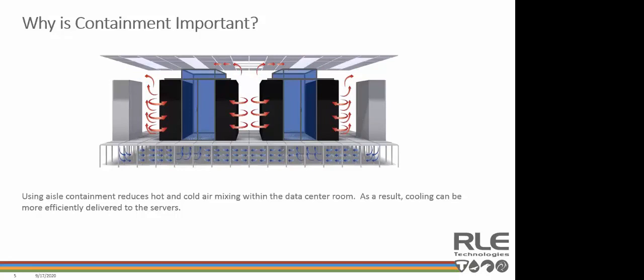In a properly contained space, cold air supply and warm air return remain separated, as you can see in the image here on this slide. This increases cooling efficiency. Ideally, cold air is only able to move through the servers, and warm air is returned to the cooling units. Without warm air and cold air mixing, it also becomes much easier to calculate the actual cooling for your IT loads. I'm going to hand it off to James now, who's going to talk about some of the cooling improvements and savings that can be gained through containment.